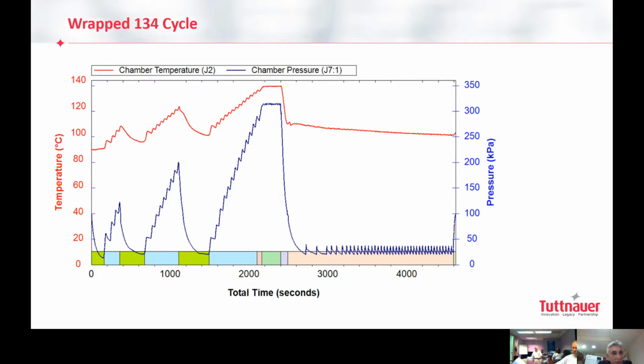In order for that, we can't use the regular gravity we know, the air jet or the top exhaust, which releases the air by pulses. We have to take action. And this is the first condition, removing more than 99%. The second condition, in order to comply with this Class B process, is being able to dry for 99%. What's the meaning of dry for 99%? It means if I'm placing into the chamber 1 kg, 1,000 gram, I'm using the European measurement unit, or in your case, I don't know, pounds or whatever it is. 1,000 gram, 1 kg.